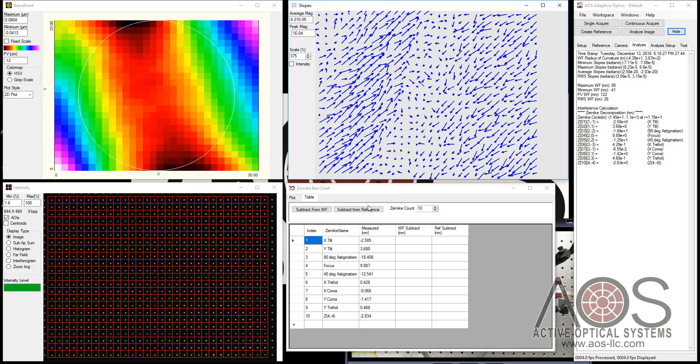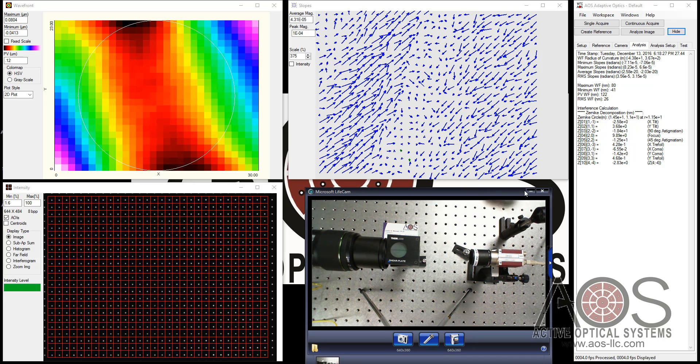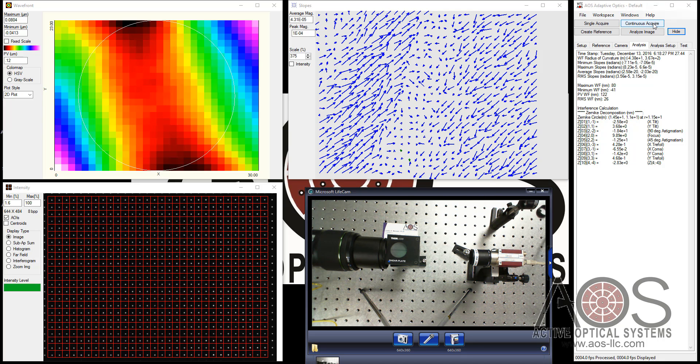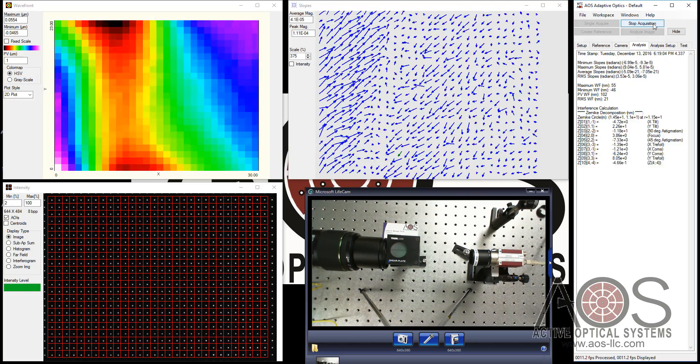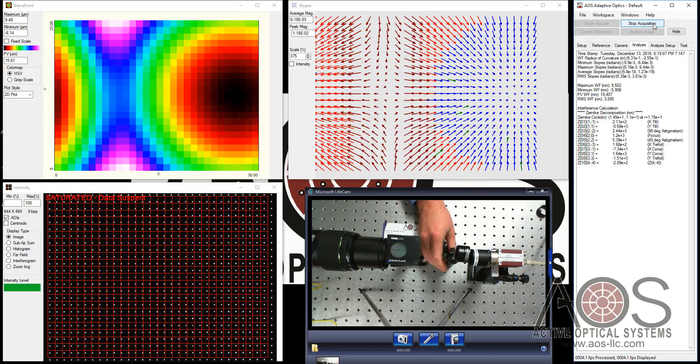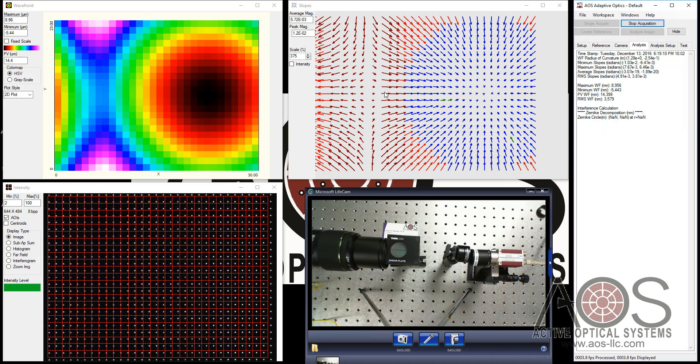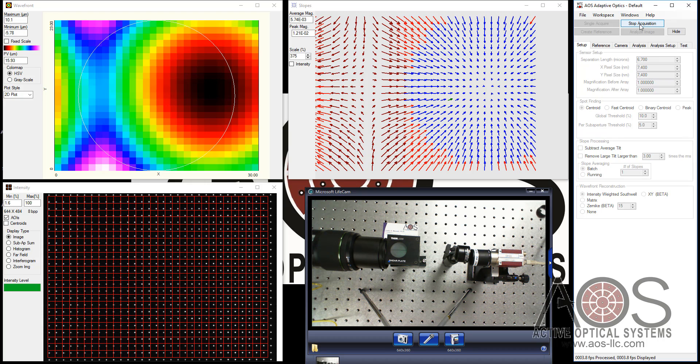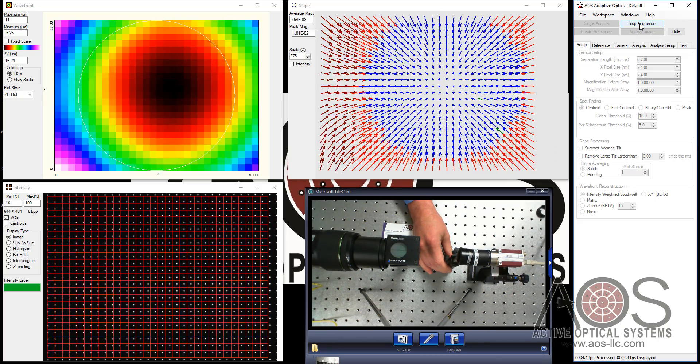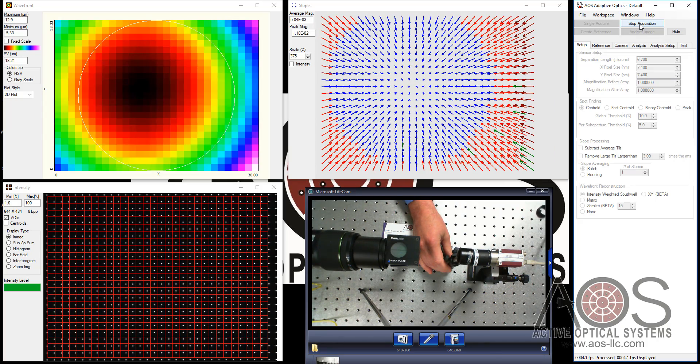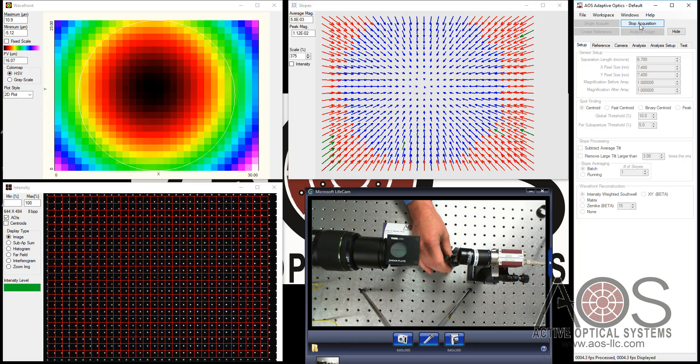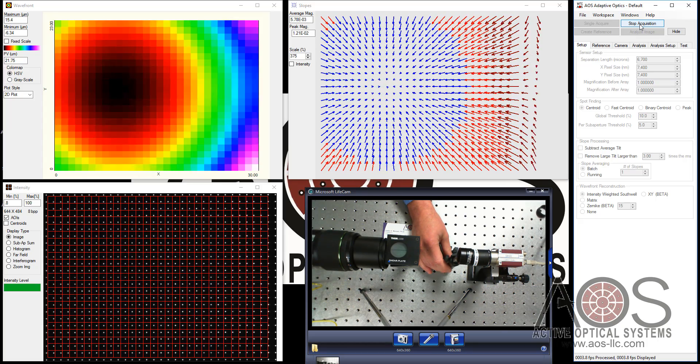So the next thing I'm going to do is try to make a measurement of a lens. I'll go back to this live view so you can see me doing this. And I'm going to try to put this lens. I'll just use the one meter lens here and put it in front of the wavefront sensor and see if we can make a measurement. For now I'm just going to go continuous acquire, slide this one in, and you see some funny things happening here. I'll explain what's going on there in a second, but I'm going to also turn off the average tilt subtraction.